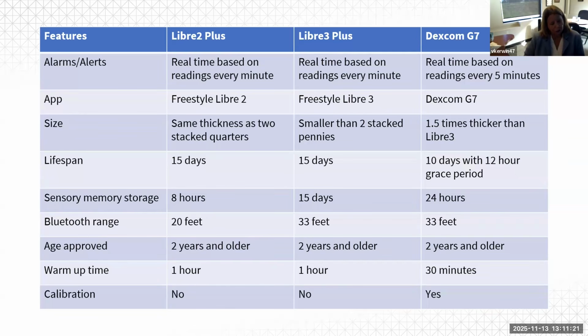As for calibration, there's no calibrations required with either of these brands. Libre 2 and 3 are calibrated in the factory, so you have no option to calibrate. Dexcom, though, does allow you to calibrate if you find you have a significant difference between a finger stick reading and a sensor and you think maybe it's not working correctly. They do have that option. You can do a finger stick, enter that data into your app and it will recalibrate the Dexcom. So that is an option for the Dexcom users.